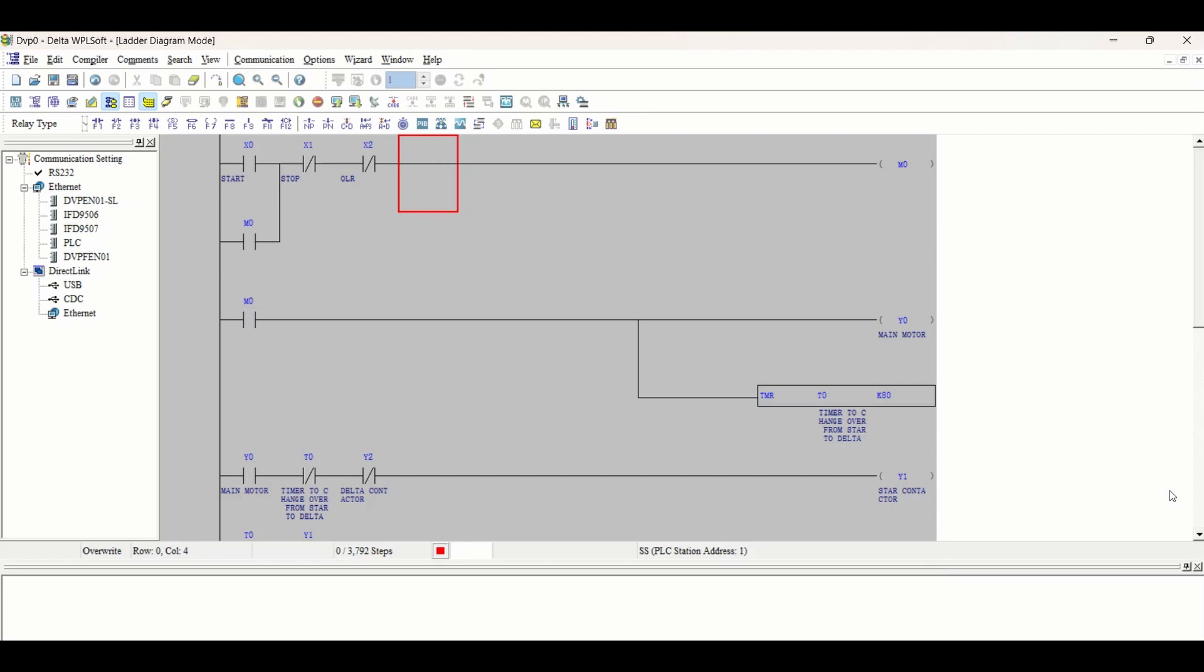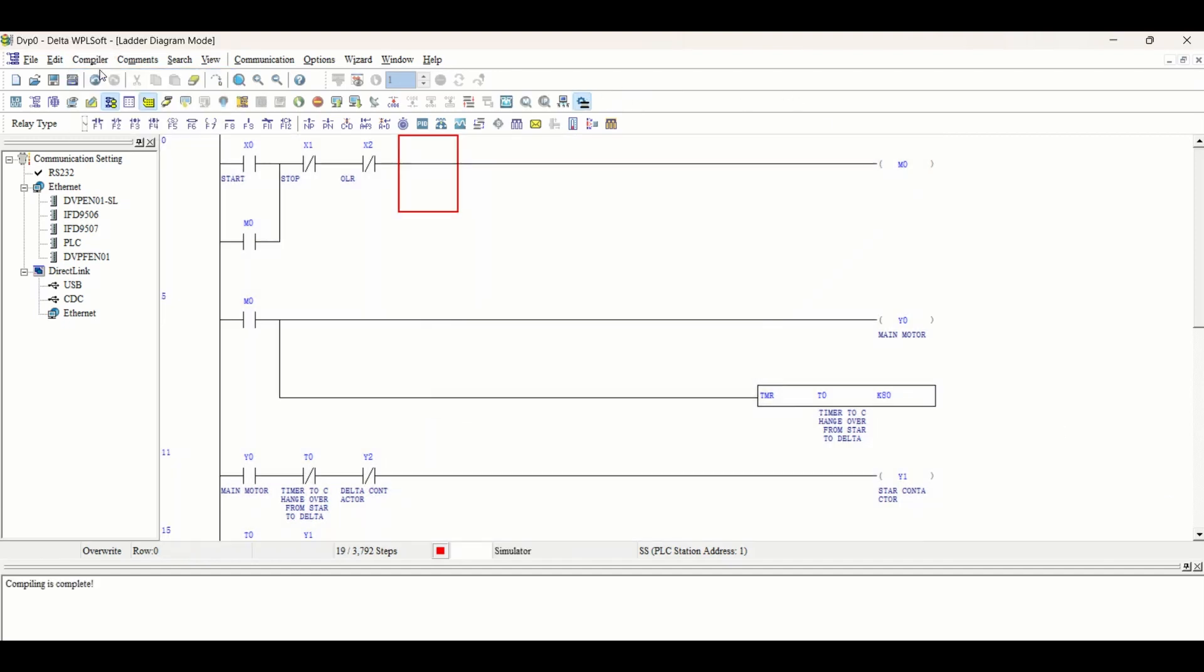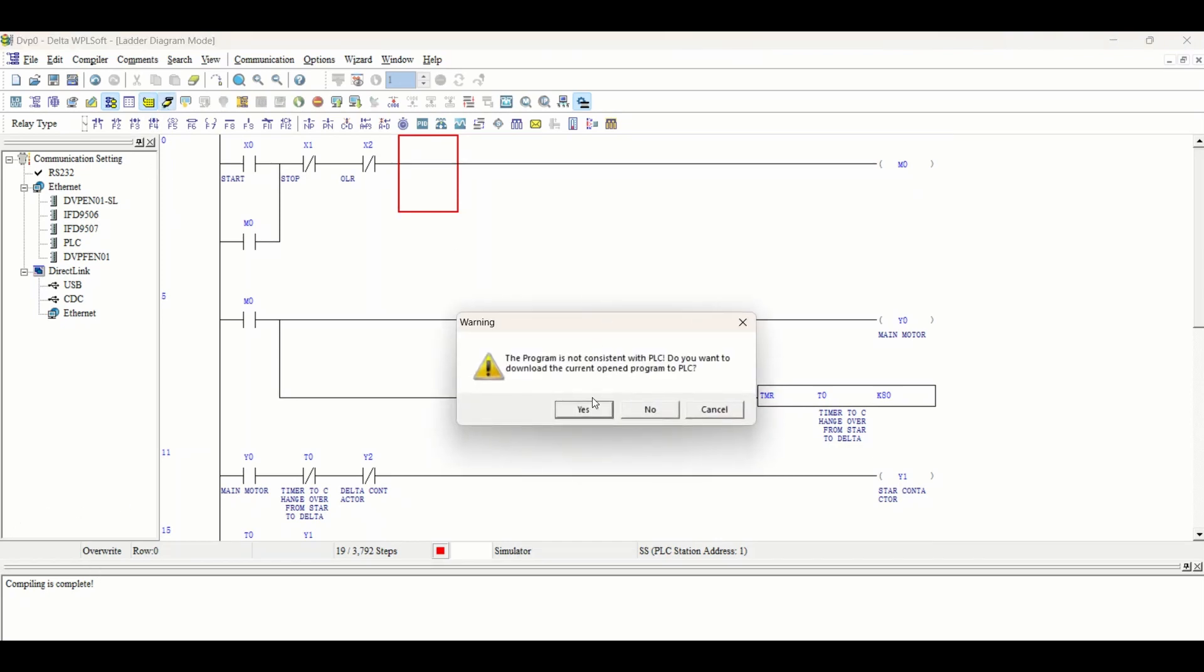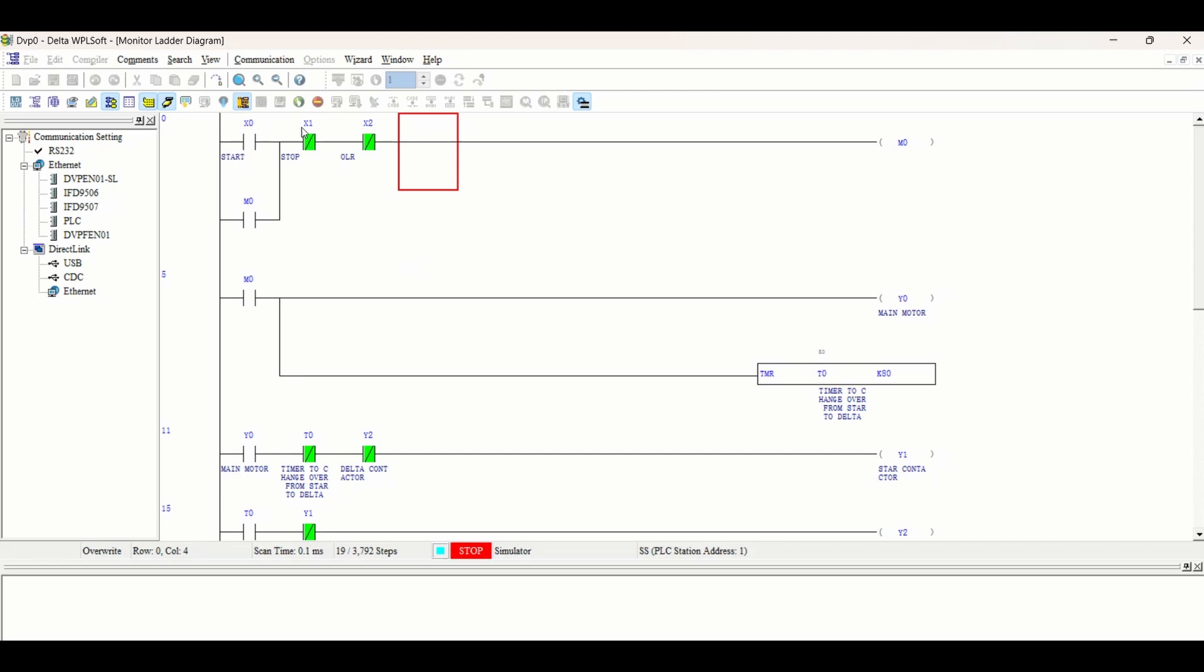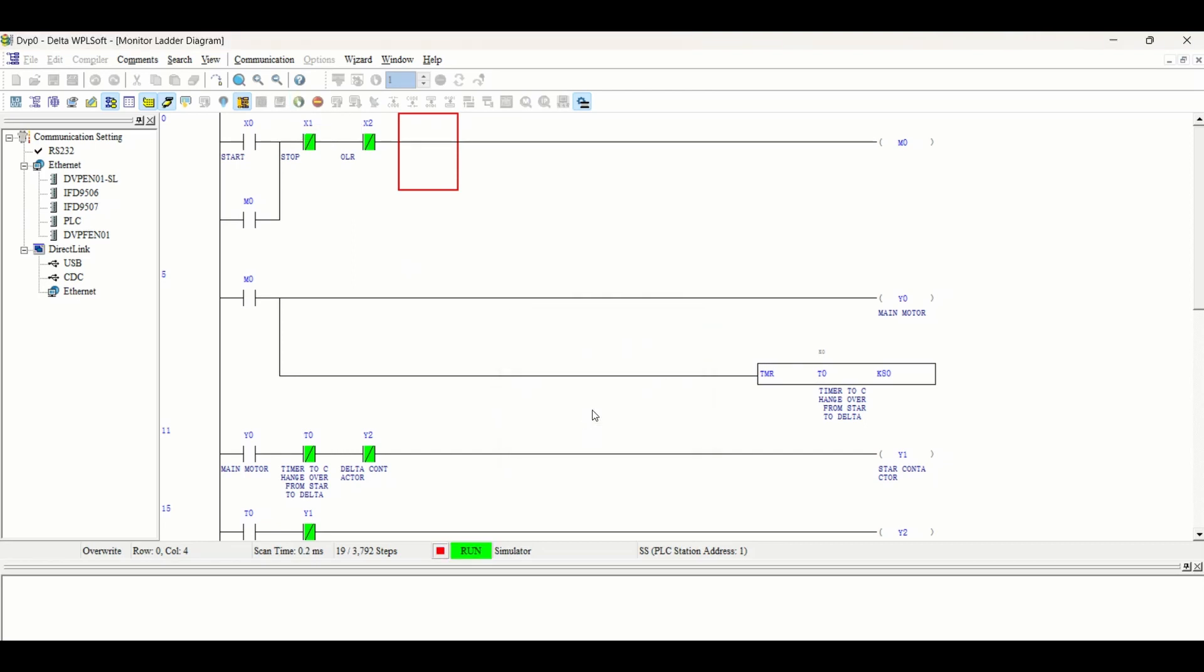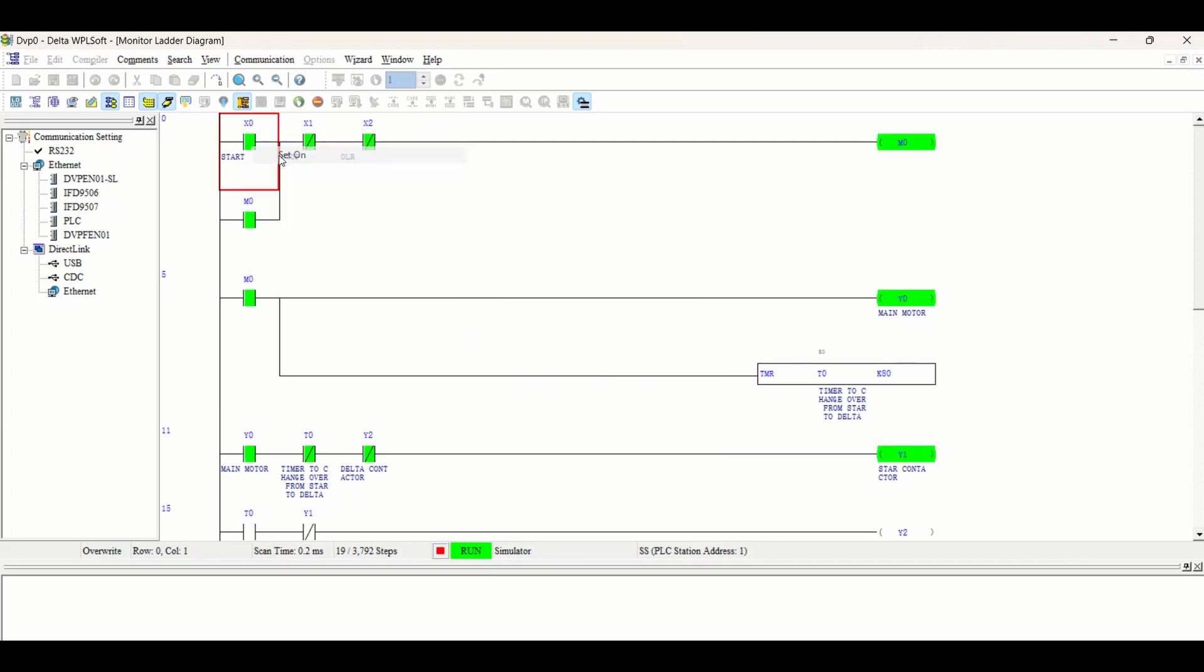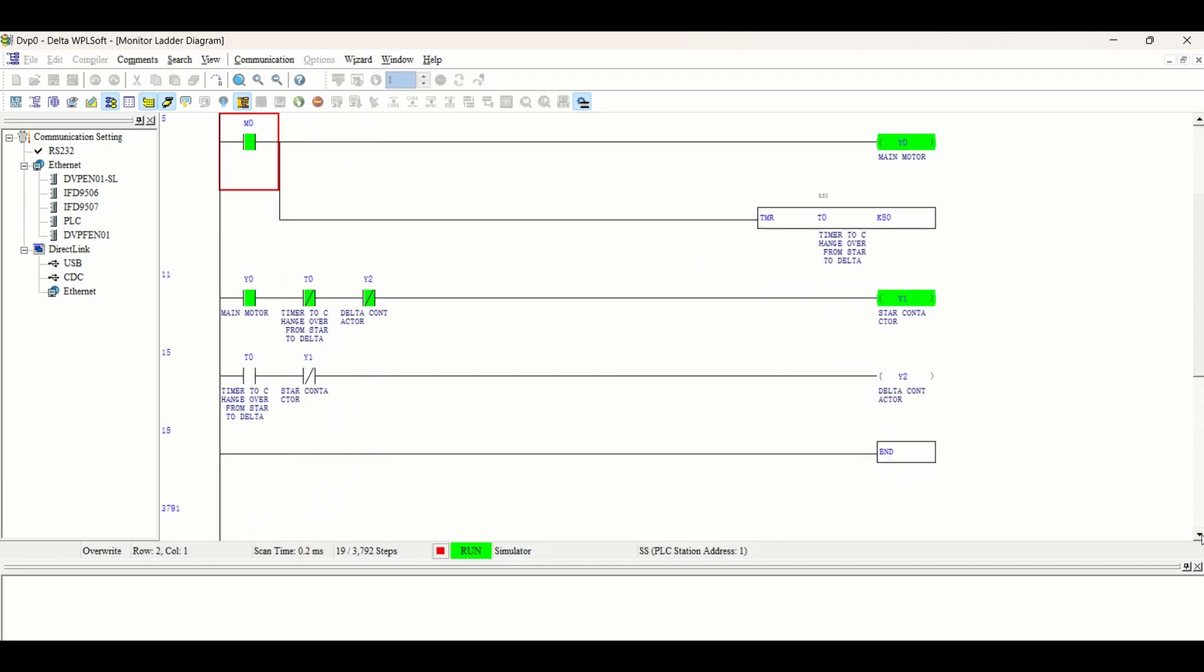Now run this program and see how it works. Go into simulation mode, compile the program - there is no error. Go online and start. I'm starting the push button. Main motor and star motor both start together, and after 8 seconds, delta contactor and main motor started. This is our star delta starter.